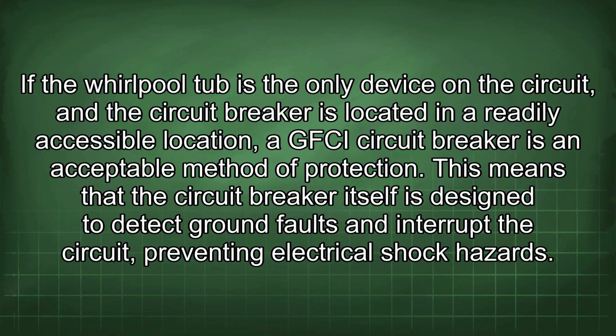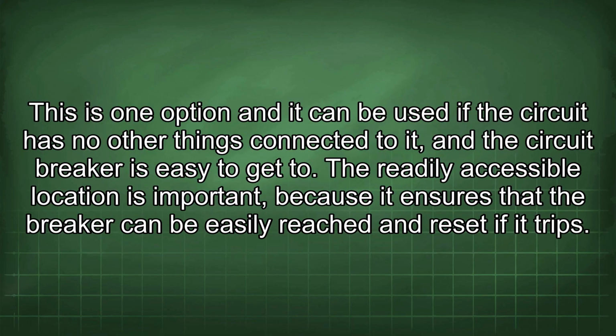This means that the circuit breaker itself is designed to detect ground faults and interrupt the circuit, preventing electrical shock hazards. This is one option, and it can be used if the circuit has no other things connected to it and the circuit breaker is easy to get to.